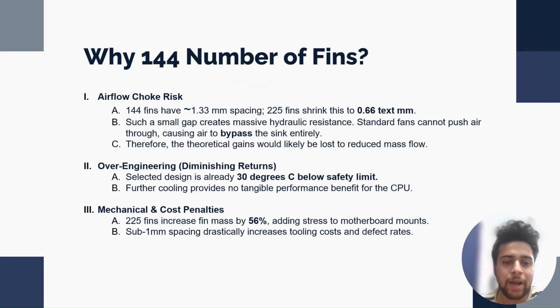Let us now see why we have chosen 144 fins. First reason is airflow choke. Whenever the number of fins increases, the spacing between each fin decreases, and this can make the air totally bypass the heatsink, as standard fans cannot push the air in. Secondly, we did not want to over-engineer our design. The requirement was only to keep the temperature below 85 degrees Celsius, and the present design already keeps it at a 30 degrees margin. So increasing the number of fins was not found suitable and feasible.